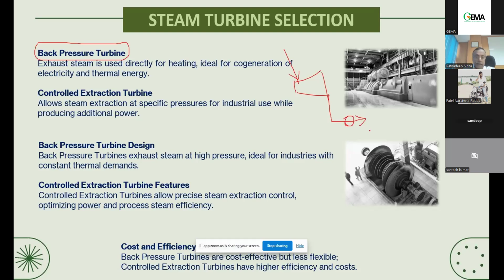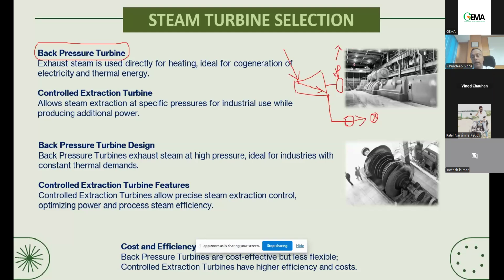But here the challenge is the control. The balance between the power and the steam is a challenge, because it is possible we do a calculation in our Excel sheet, in our model, in our HMBD, but end of the day, if the power demand goes high and your steam demand is fixed, I cannot increase the power, because my steam demand is fixed. I cannot put the steam anywhere else. So however much steam I give, the power will increase in that proportion. Or if I demand more steam and my power is fixed, I also cannot extract more steam, simply because I cannot give the power to anybody else.